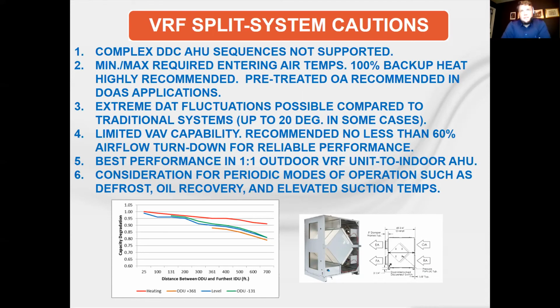In the Chicago market, I always recommend 100% backup heat in critical applications where you might be trying to use it for DOAS or even just really tight temperature control. I've seen these systems be extremely successful in cooling-only applications where you already have your heat figured out, whether it be hot water, electric, or gas. If you're just using it for cooling only, VRF systems paired with a third-party coil actually do pretty well.